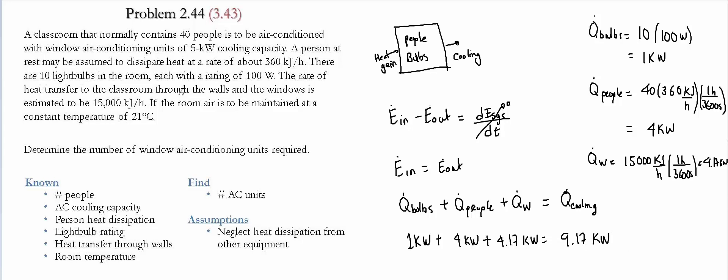The goal is to determine the number of window air conditioning units required to maintain the temperature at 21 Celsius. We need to remove 9.17 kilowatts of energy from the classroom. One unit is not sufficient since each only has 5 kilowatts of cooling capacity. Numerically, we need 9.17 divided by 5 equals 1.83 units. Since we cannot have 1.83 units, we round up — we need 2 cooling units to maintain the temperature at the desired 21 Celsius.